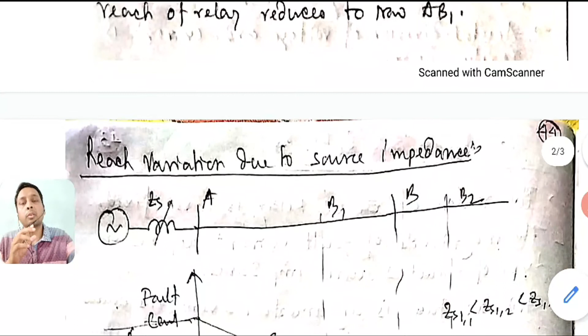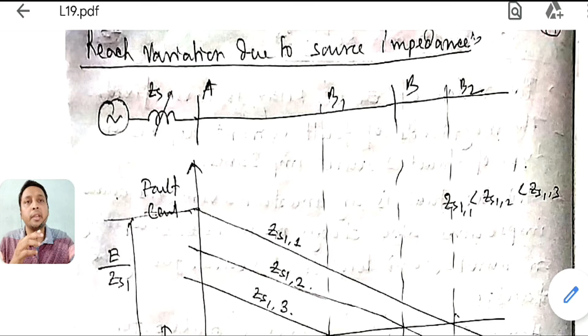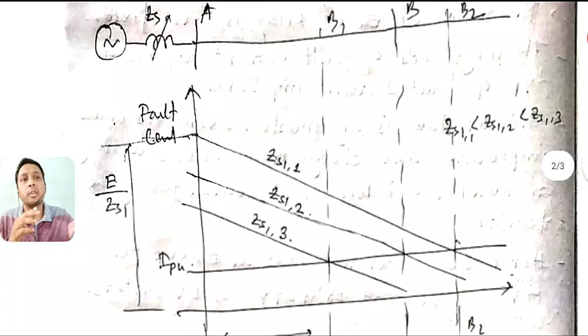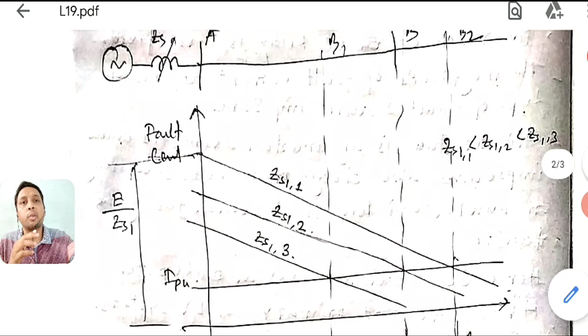So one more effect due to which the reach changes is source impedance variation. Here I have shown you the effect of source impedance variation. You can see that your source impedance ZS is not a fixed quantity. I have given a variable sign to indicate that it is varying, because you don't know at the time of fault what generator will be connected, how many generators will be connected, or what the source impedance will be. As impedance changes, your fault current will also change. Fault current will be E divided by ZS plus ZL, that is, up to the line section where the fault occurred. That is the fault current.